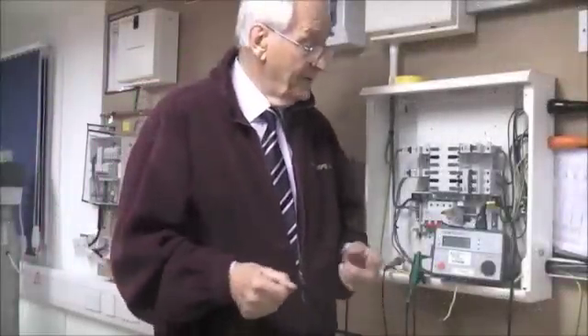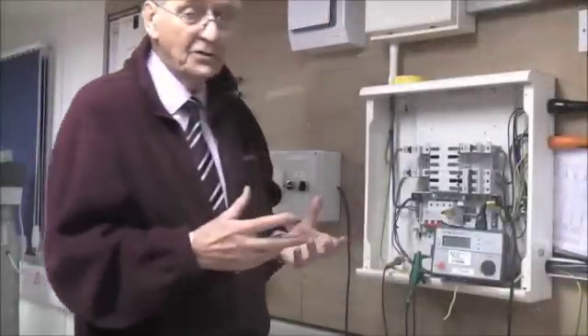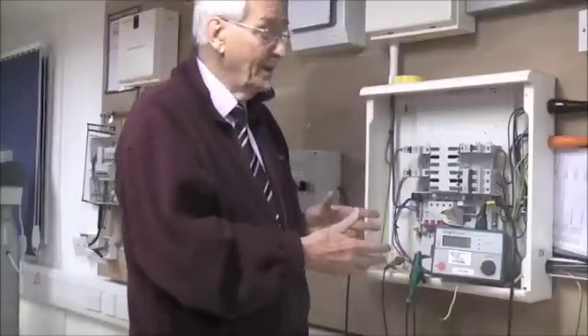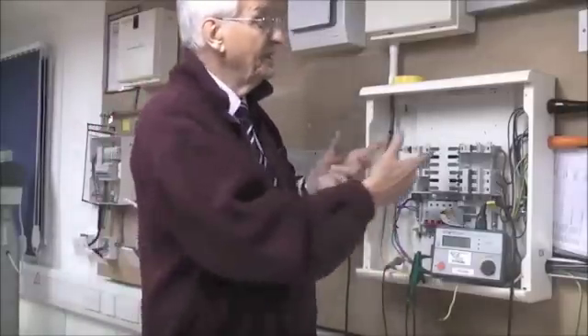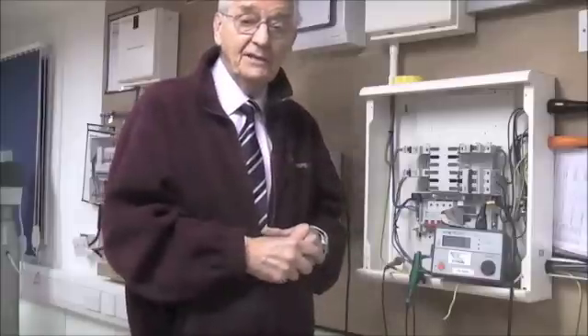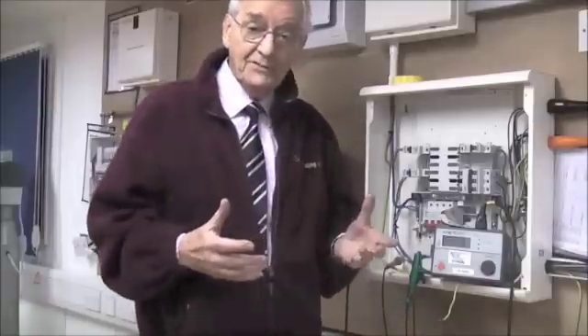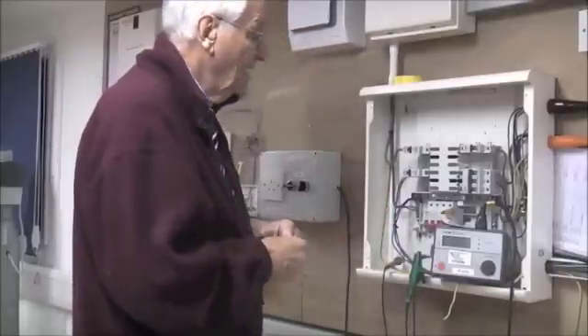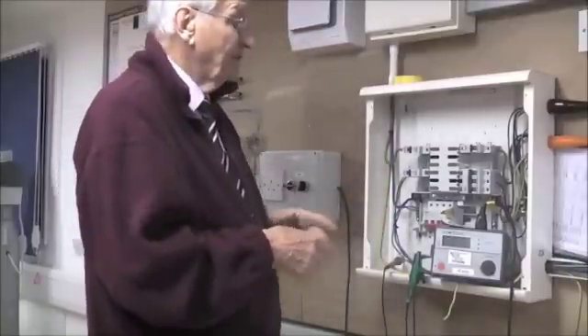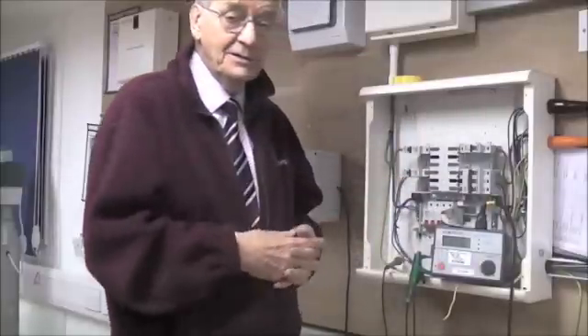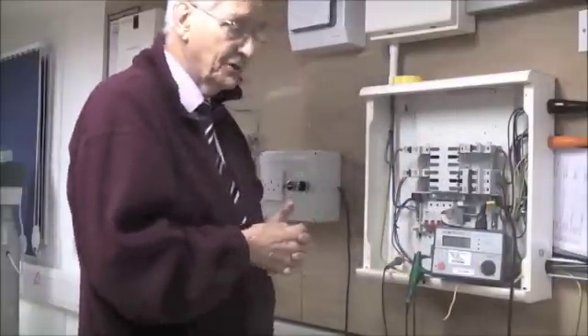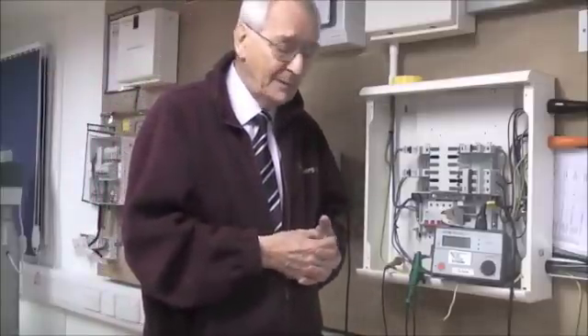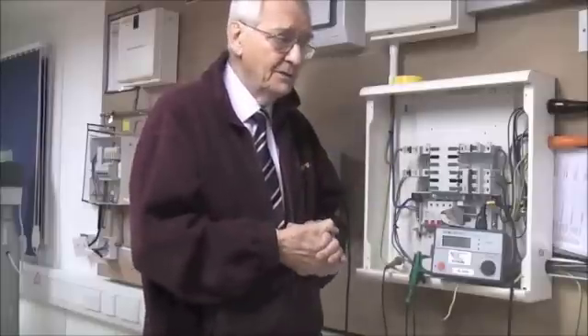So there you have it. We've taken all necessary precautions. We've carried out a proper ZE test at this board. We can compare those readings to the MCB ratings and the time of disconnection with BS 7671 and following that we can move on. We mustn't forget of course to restore this distribution board back to its safe condition, operational condition. Warn everyone that the supply is about to come on. Make sure everybody's happy with that and then we can restore the supply to the installation.